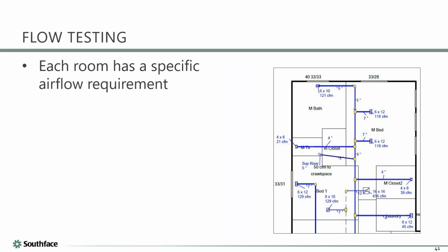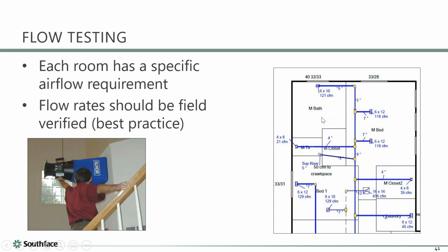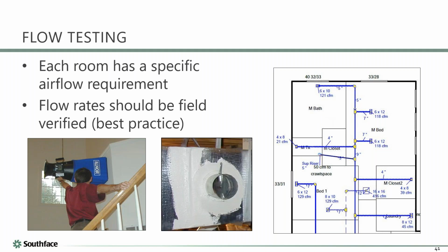In terms of really making it work, it's great to take your duct design and then commission it. And we commission it by using a flow hood, and we can verify that we're getting at least within 10% of the design airflow. And we might actually invest $2 for a balancing damper on each supply run, so we can really adjust the airflow. It's like, that's crazy. What a crazy idea. We'd put dampers in our system.